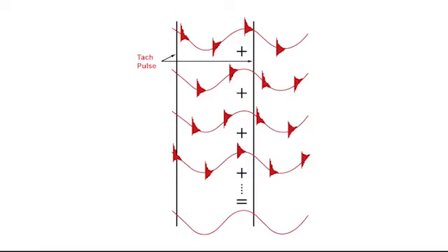The starting point of the waveform in the snapshot is more or less random. In synchronous analysis, the starting point of the snapshot is always the moment that the tach pulse is detected. So we start from the same shaft position each time, and instead of averaging the spectra, we average the waveform. Because the waveform is always starting with the tach pulse, and the position of the shaft is always the same, the data will be very consistent. We call this synchronous data.